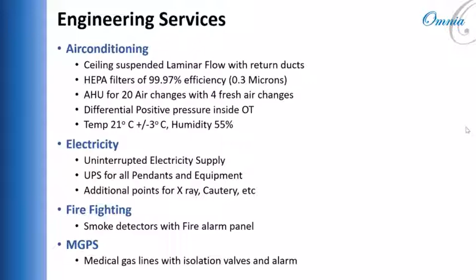Firefighting, this is a very important area. We need to have smoke detectors with a fire panel. We can't provide sprinklers inside the OT, but smoke detectors should be placed inside the OT as well as above the false ceiling, in the corridor area, and in every support area we have discussed. It should come with the fire alarm panel. Then there is MGPS, the medical gas piping system. All medical gas lines with isolation valves and alarms should be placed.